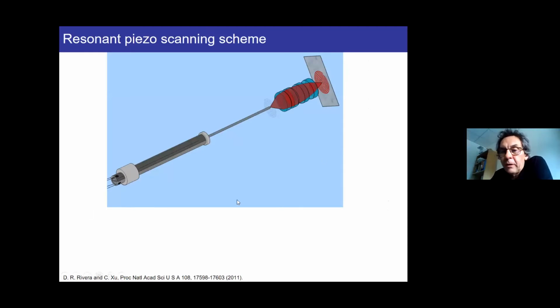So now a few words about the device, which is the scanner itself. We want to make an imaging system which is tiny, which is small. So what we are using is a piezo scanner. This cylinder here is a piezo tube. It's made from piezoelectric material that has the ability to change its shape when you put a voltage at the entrance. Actually, there are 4 cables because it is a 4-quadrant piezo system where you can scan along X and you can scan along the Y axis as well.